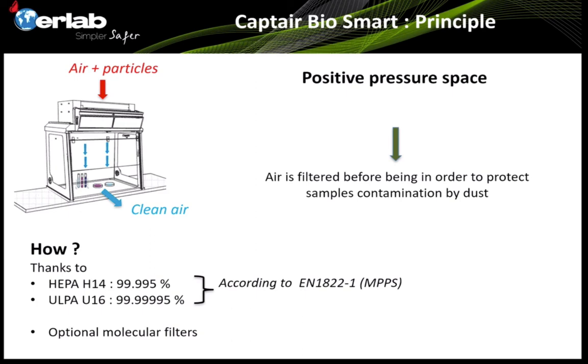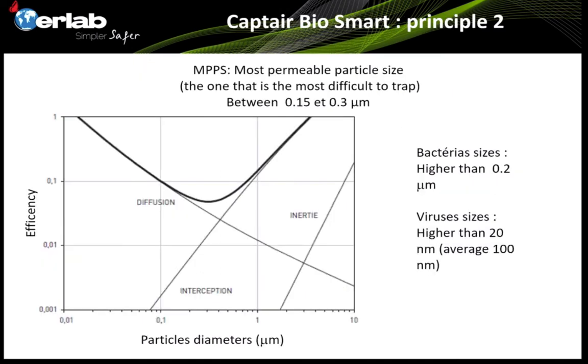CAPTAIR BioSmart can also be combined with optional molecular filters. Researchers have shown that in certain cases, VOCs in the atmosphere can also contaminate PCR amplification, and in certain circumstances it is very important to protect samples against VOCs. Here is a drawing that shows what can be trapped by HEPA filters according to EN1822-1.